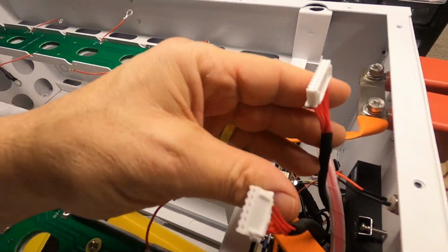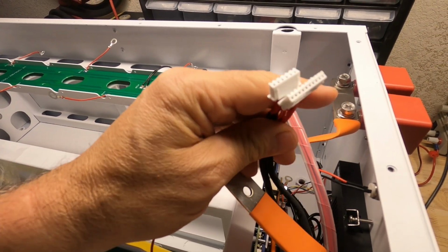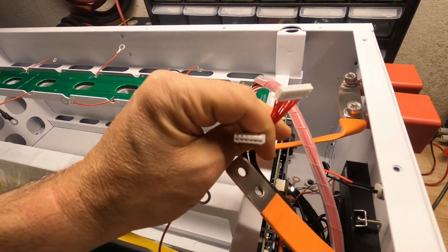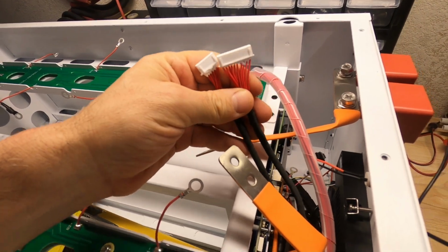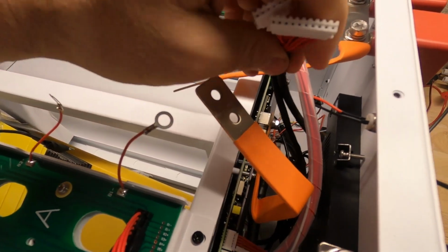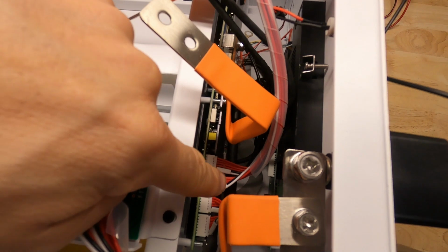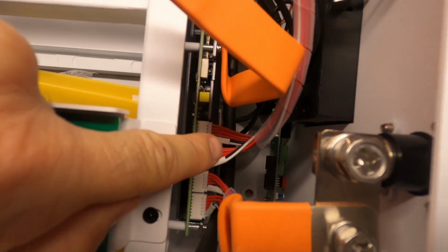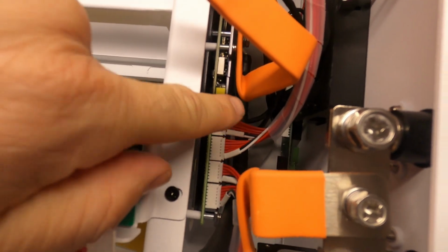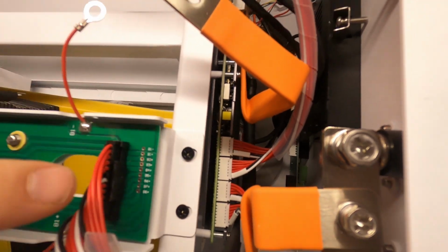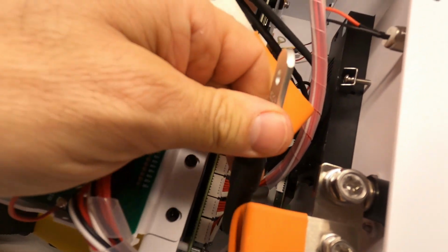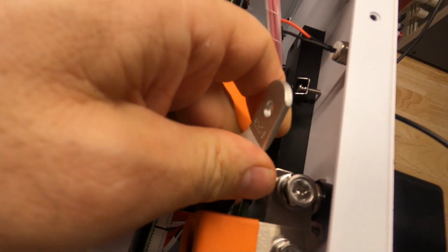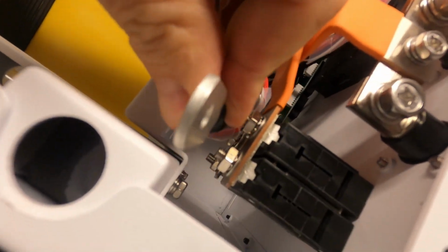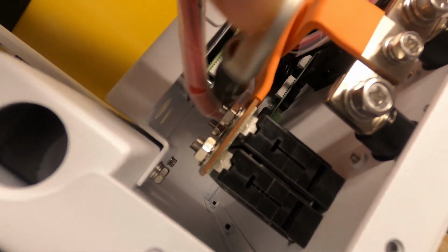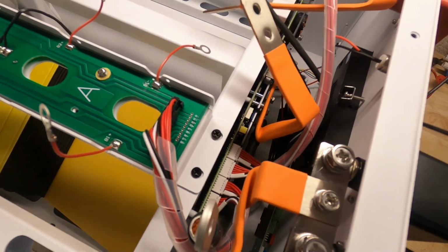Another thing, the comms cables for the BMS harness come disconnected. This has to connect to the comms PCB board, which is down there below the BMS on the bottom of the faceplate, and also the main battery P- here that connects over to the breaker right there comes disconnected as well.